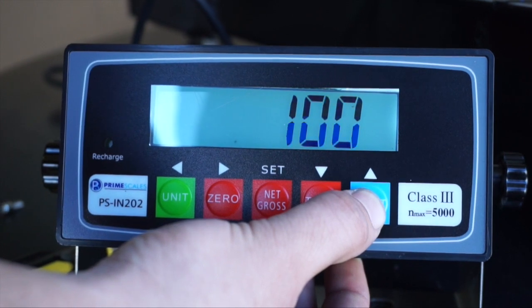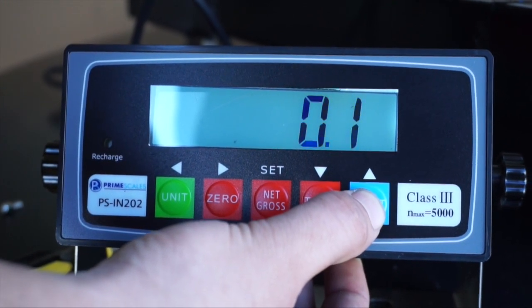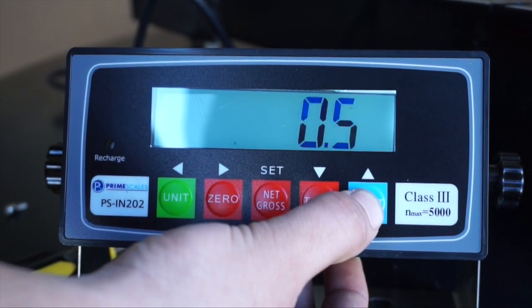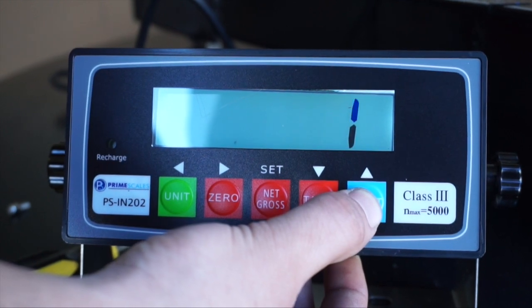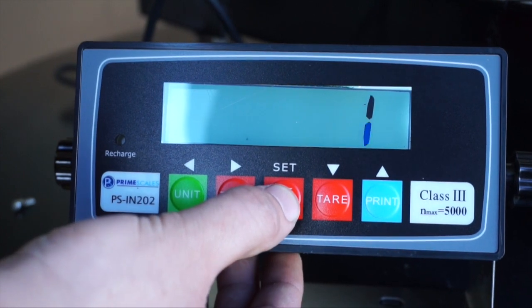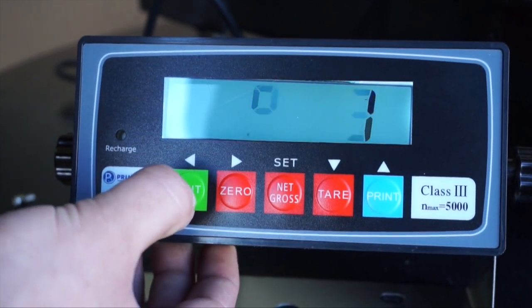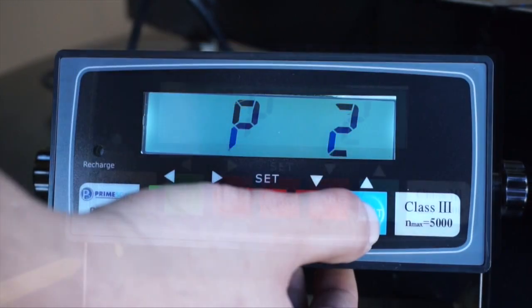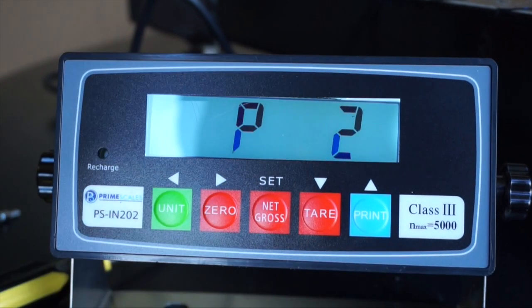With the print button, you can choose between 1, 2, 5, 10, 20, 50, 100, 0.1, 0.2 or 0.5 of a pound. We will set the accuracy at one pound for this scale. Save settings by pressing the net gross button. Press unit to return to parameter menu.